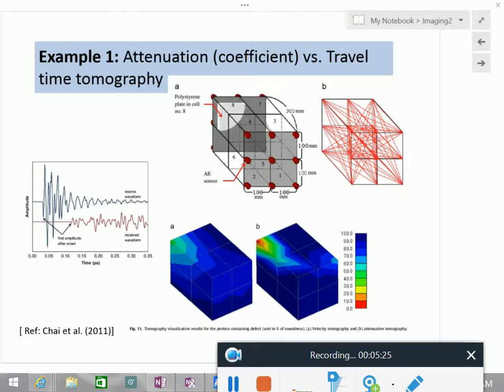So if these transducers, if all these sensors are not well calibrated, the attenuation at one is not equivalent to the attenuation you get from the other one. So for those of you who know Jacques, who is almost everyone, he's now making an imaging system like that, and this is one of the problems he has, because he's making his own sensors, and of course they're not calibrated. So to measure attenuation, it's a big dilemma, right? To do it correctly. So that's why everyone sticks to velocity.